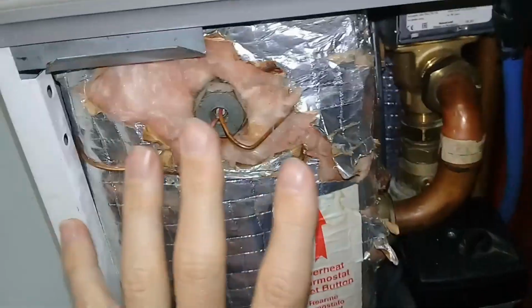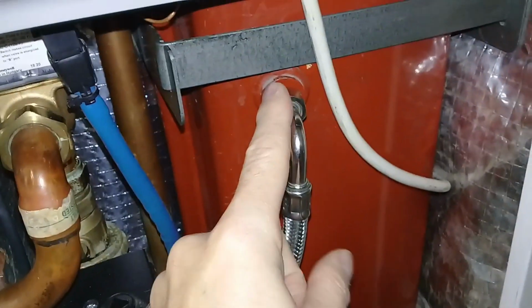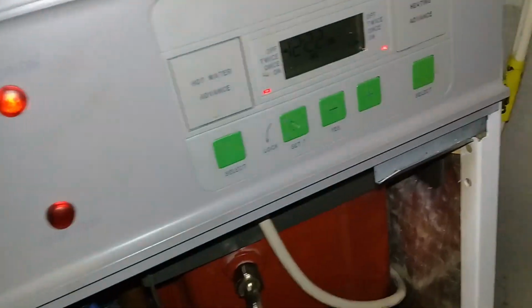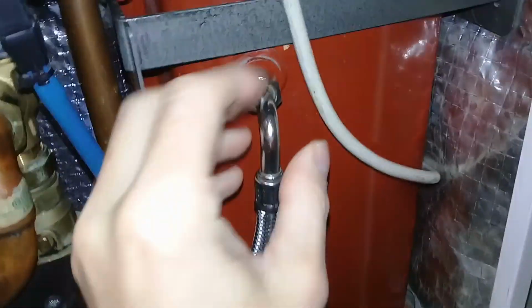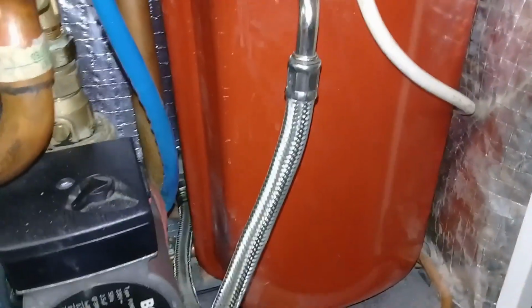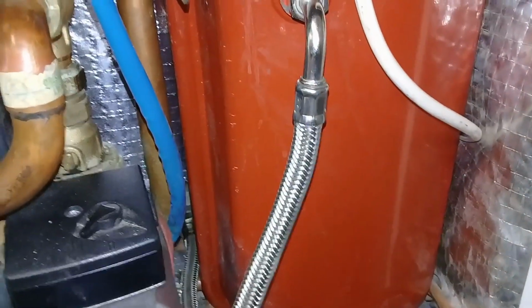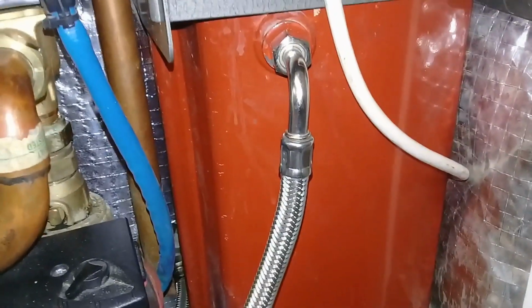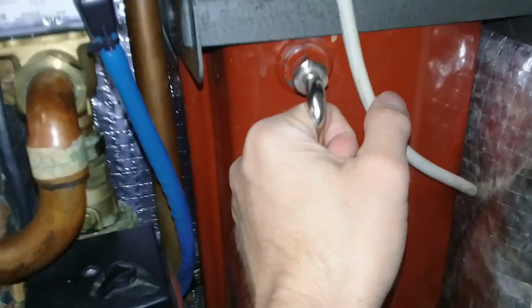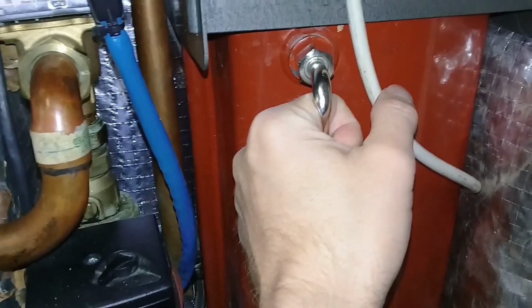drained the system. Once the system was completely drained, including the heat store, I undid this carefully. No pressure in here after checking this valve. Well, it went psst, and that was it, so it's obviously no pressure. I disconnected the pipe, pulled the pipe off, blew it, and I think it cleared a small blockage. This system's fairly clean, but it wasn't when we first moved in. So blowing the pipe cleaned what blockage I thought there was.